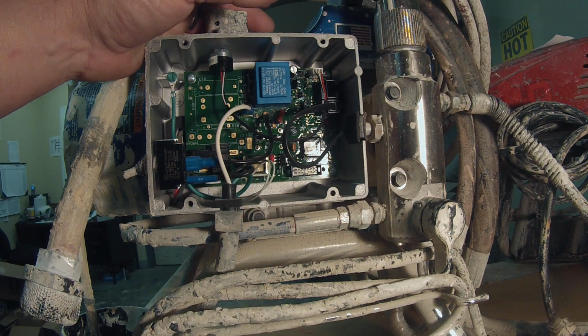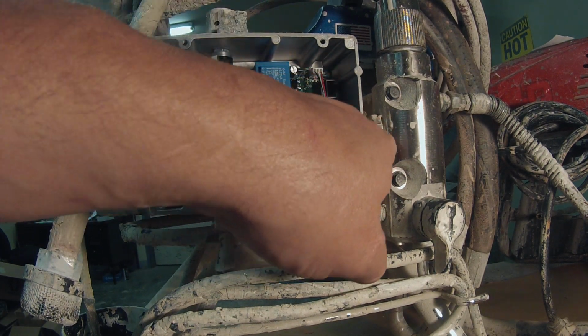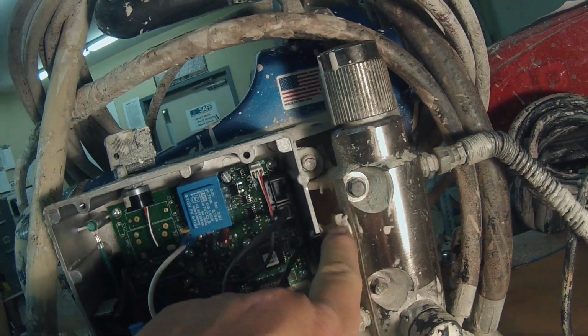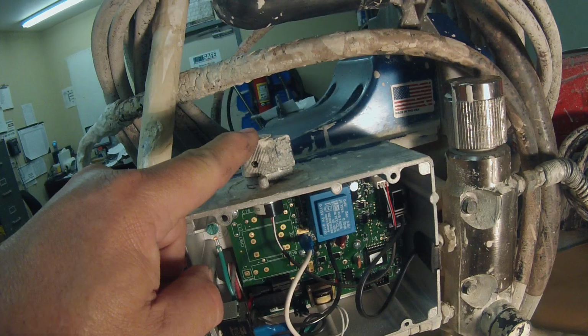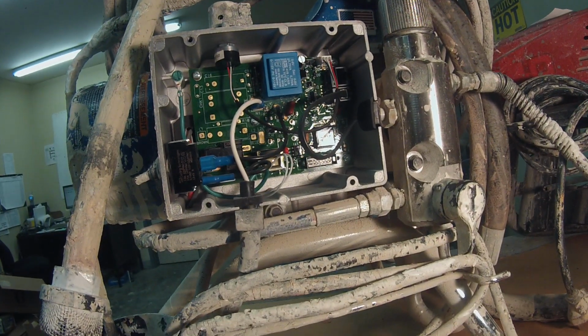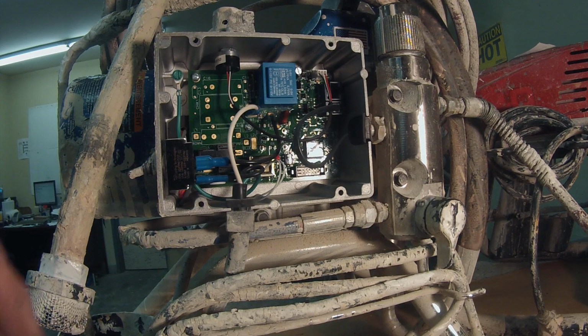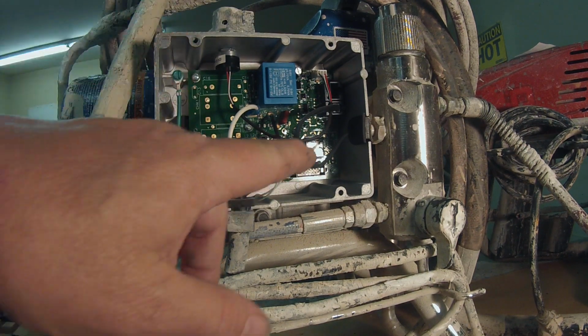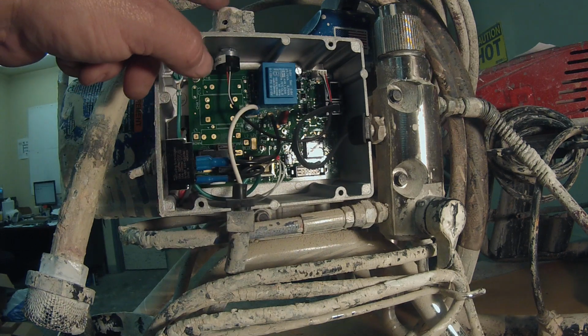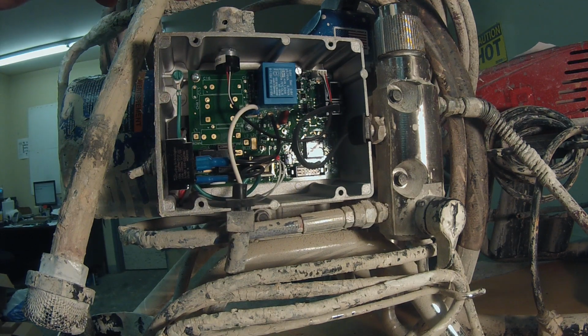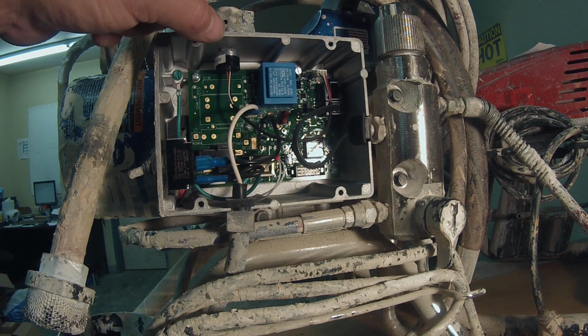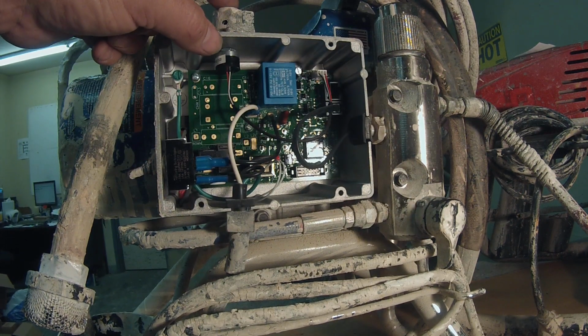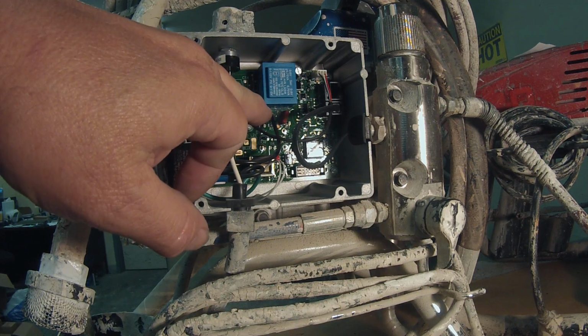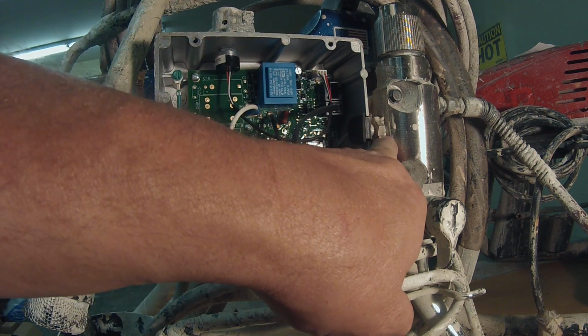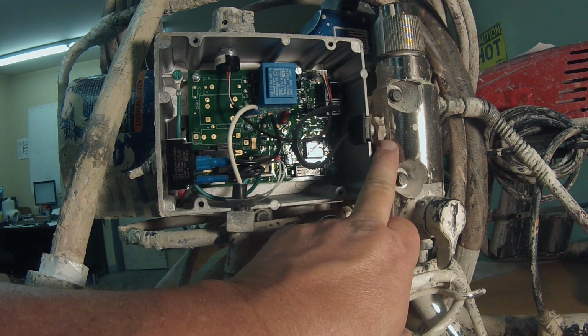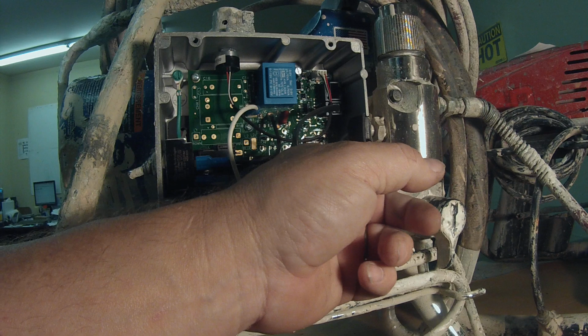A 390 is different. It does not have a transducer, which is this item here inside of your filter manifold. It does not have a potentiometer. On the 390 you have a pressure control, which is different from the 395 and above, where you have a transducer and a potentiometer. The purpose of this is to control your pressure. The potentiometer sets the pressure. The computer then monitors your transducer. Your transducer measures the pressure that is being achieved in your filter manifold.